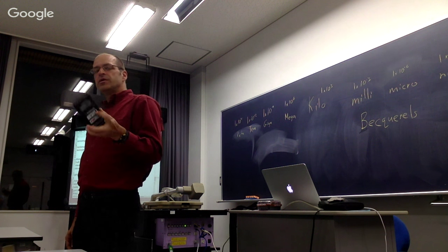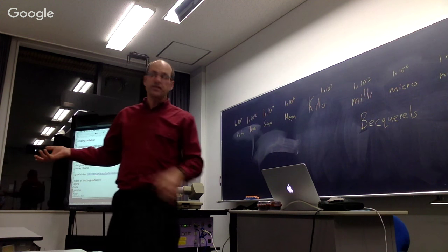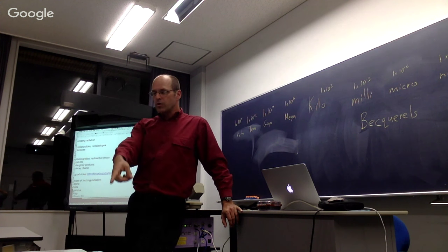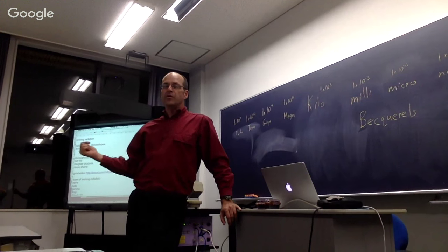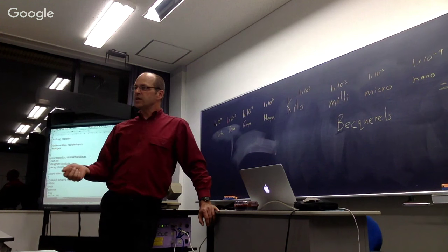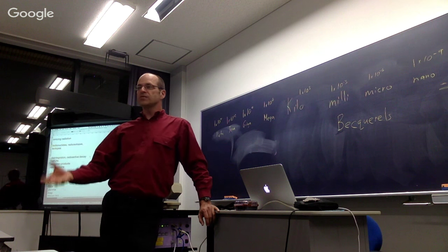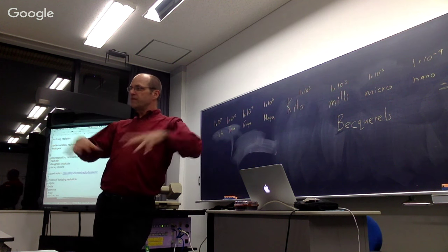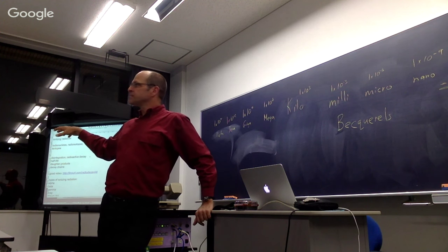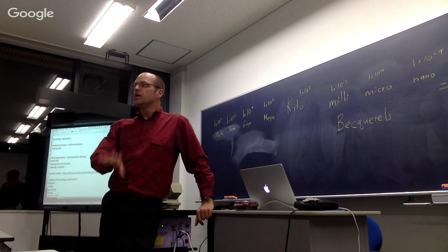In dose mode, we know what the contamination is in Japan now. It's cesium. So we use a conversion factor to get to dose rate based on what we know about the tube and what we know about the contamination. We do that by having a few detectors that can tell the difference. We have a scintillation detector, a very expensive, very sophisticated piece of equipment, but we use that to leverage a lot of very inexpensive detectors. Using that, we were able to characterize the contamination environment and know what factors to multiply the number of counts by to get a dose rate.